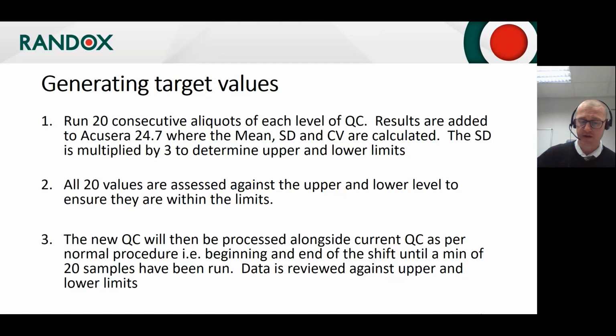So once we've done these 20 values, we then assess them against the upper and lower limits which we've generated to ensure that they are all within the limits. If a value exceeds either limit, we remove it from the data. The SD is recalculated, and if required, subsequent runs will be performed to ensure the statistical validity of the data. By convention, 20 values is deemed the minimum for valid statistical analysis. So once we've done this initial 20 value run, that's what we call our intra-precision run.